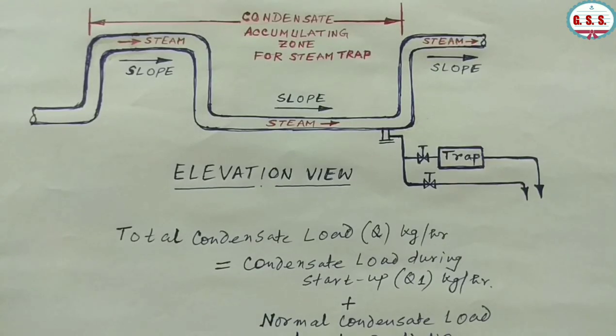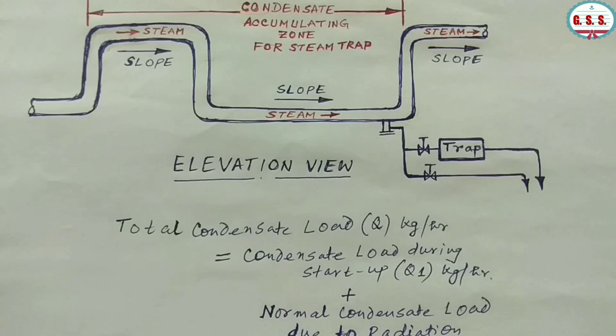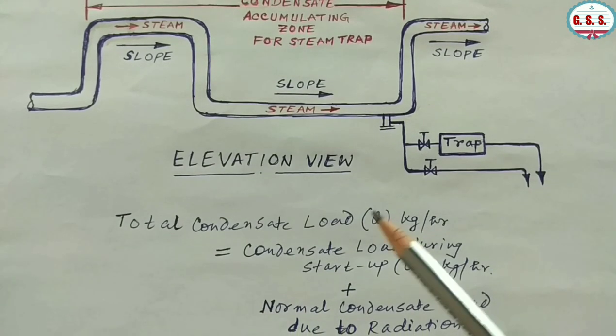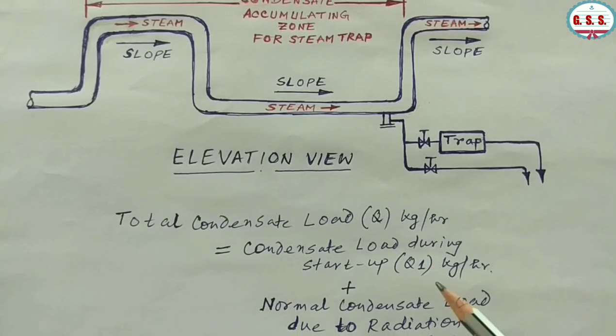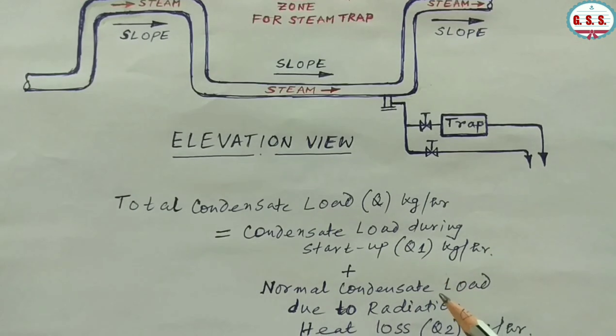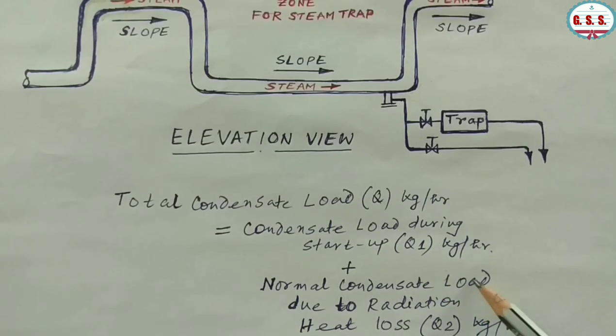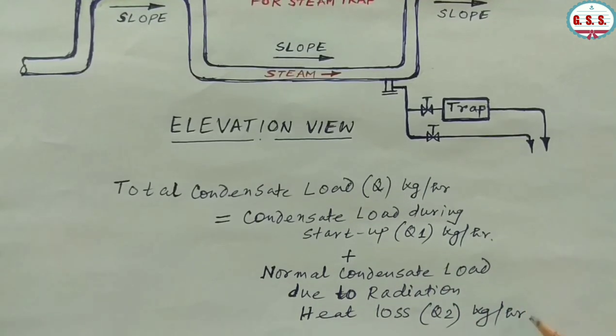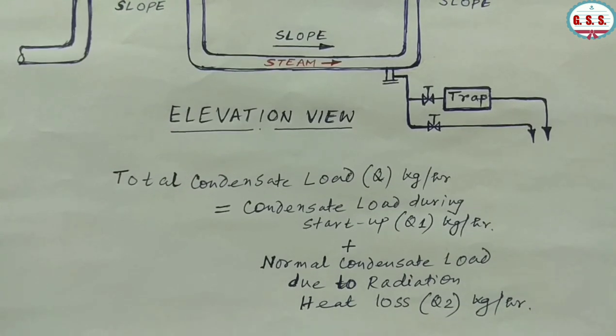For designing a steam trap, total condensate load Q (kg/hr) equals condensate load during startup Q1 (kg/hr) plus normal condensate load due to radiation heat loss Q2 (kg/hr).